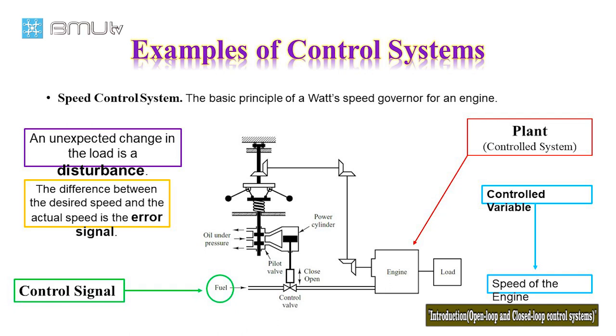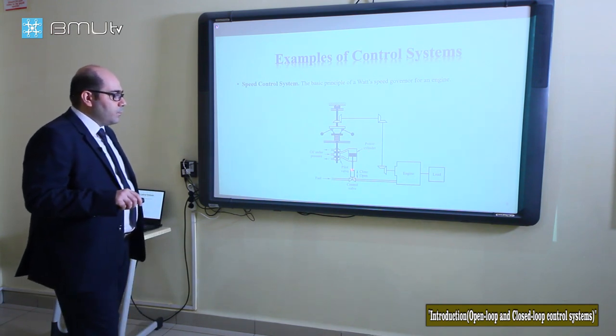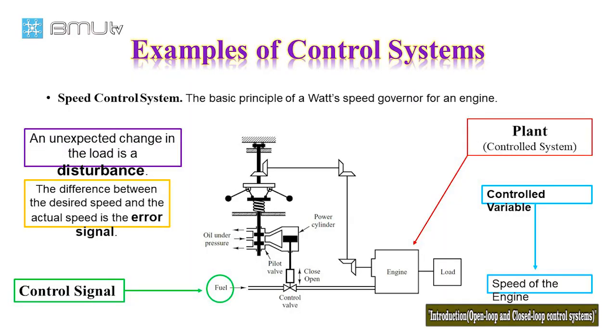If the actual speed of the engine drops below the desired value, the governor speed decreases, so the control valve moves downward and more fuel enters the engine, causing the speed to increase until it reaches the desired value. On the other hand, if the speed of the engine increases, the control valve moves upward, decreasing the amount of fuel going to the engine until the speed returns to the desired value.